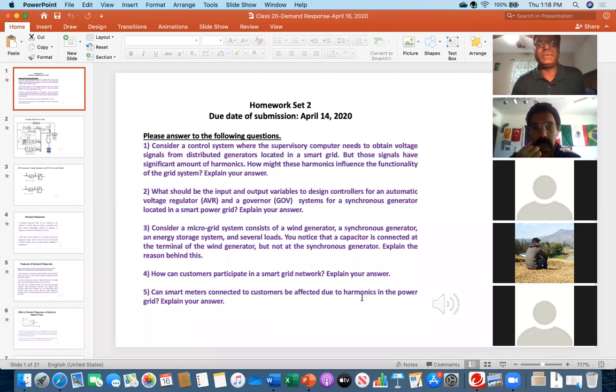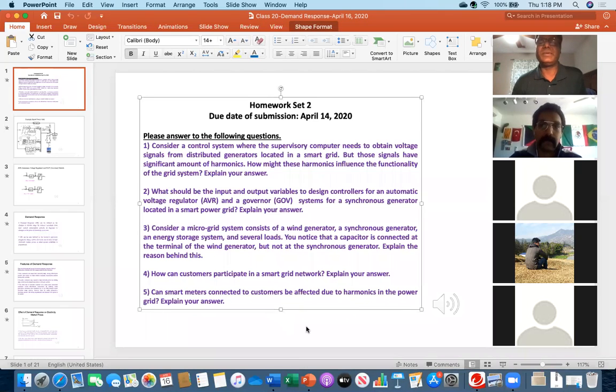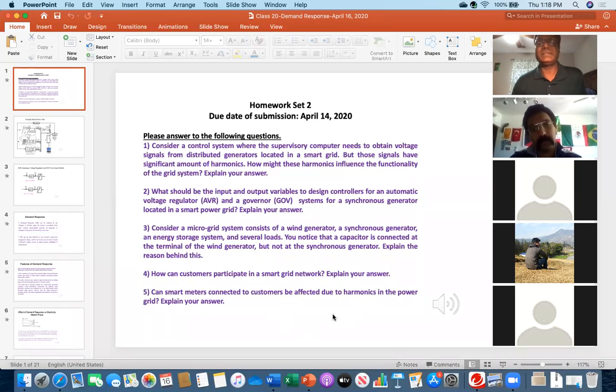Because harmonics are undesired or oscillating signals entering the system, smart meters might not understand those and consequently might provide a wrong reading or wrong output. In other words, smart meter performance could be affected due to harmonics, and the consumer reading might not be correct because of higher order frequency signals, since smart meters are typically designed to consume only sinusoidal signals.